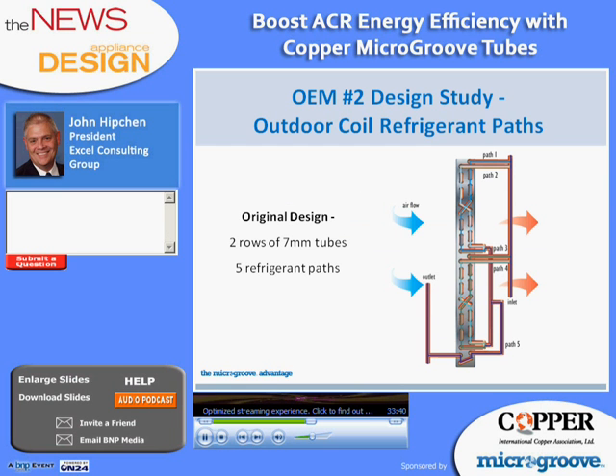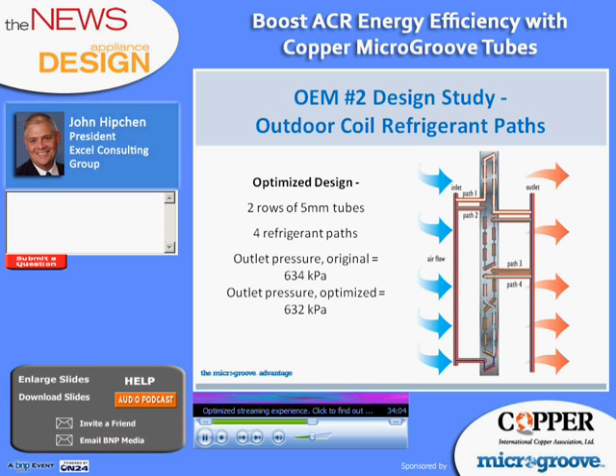When we look at the original design circuit diagram, we see some T's and some sharp 90-degree turns in the refrigerant path. And when fluid makes a sharp, sudden change in direction, like we see happening in this circuit diagram, it can cause a considerable pressure loss and be restrictive to the flow of refrigerant. In the optimized design, T's and sharp turns are minimized. This less restrictive routing could be one reason why we see fewer refrigerant paths in the optimized design, even though we are now using smaller diameter tubes.